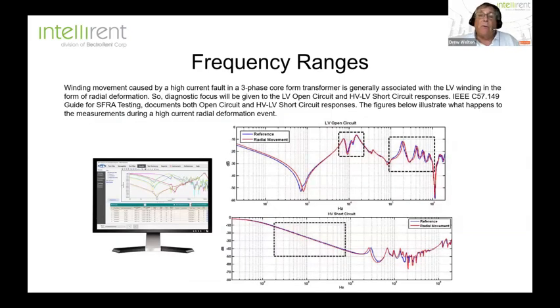Well, one of the things that we do know, and again, this is in C57.149, is that if you have physical damage based on a high through fault or a series of through faults, that's generally going to be associated with your low voltage winding in the form of radial deformation. So your diagnostic focus for your SFRA will be your low voltage open circuit test and your high voltage to low voltage short circuit responses. And again, this is all documented in the IEEE document.